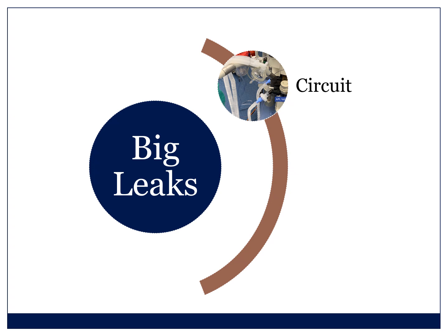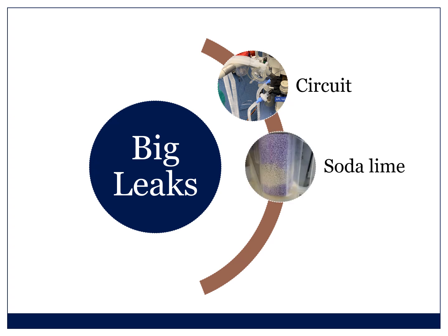One of them is the circuit. And usually what I mean by circuit is there's a disconnection. One of those limbs has come off, the expiratory or the inspiratory limb. So check your circuit is attached to the tube, and attached to the machine. Second big one is soda lime, especially if someone's changed the soda lime. It just hasn't been closed properly, or it hasn't been sealed properly.